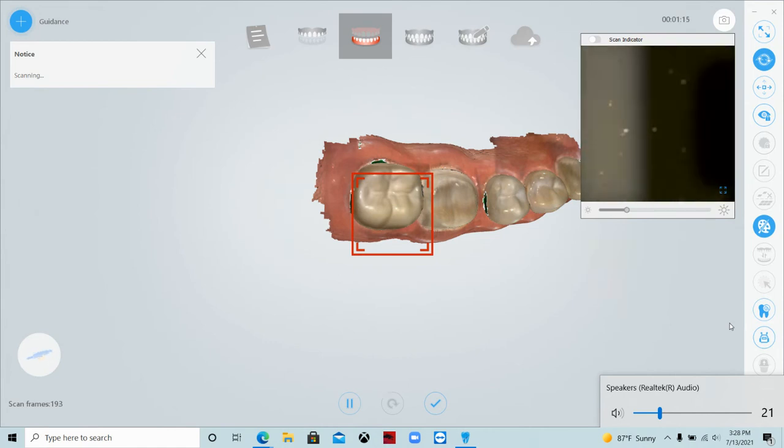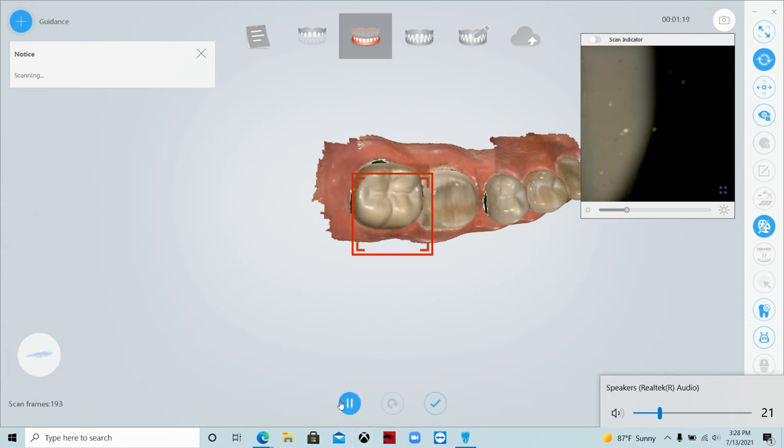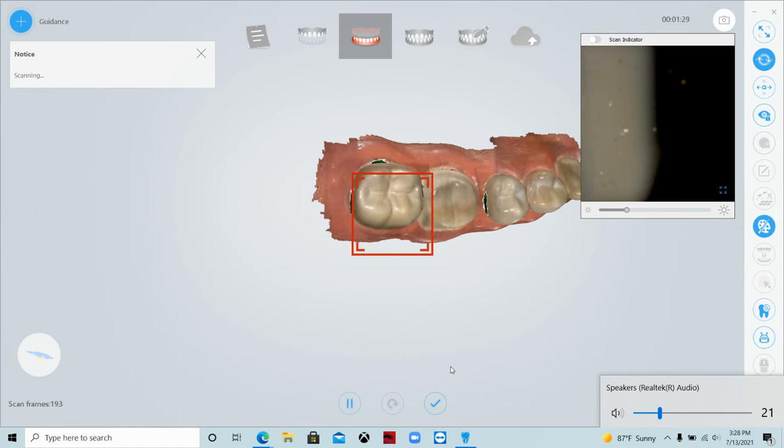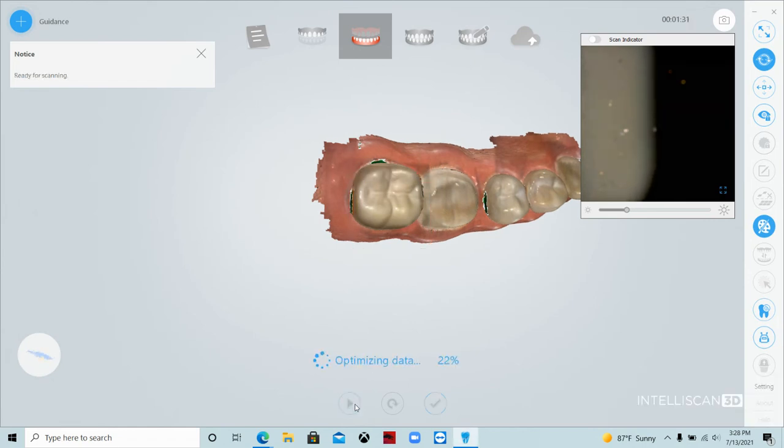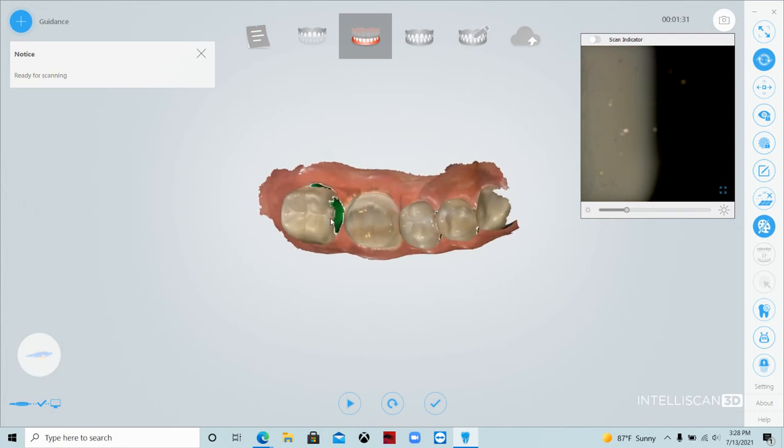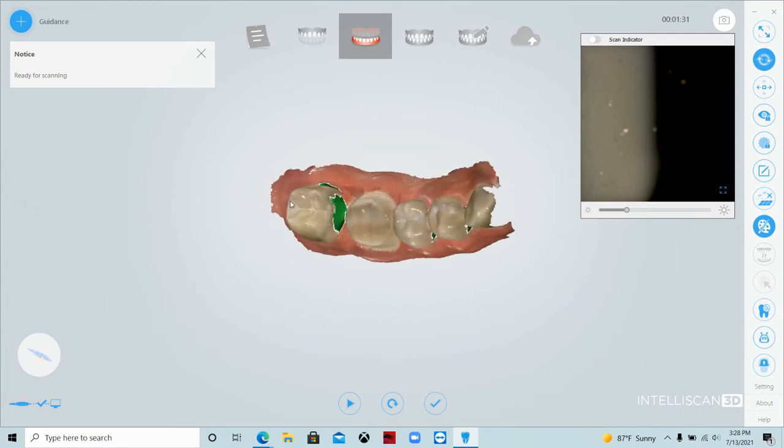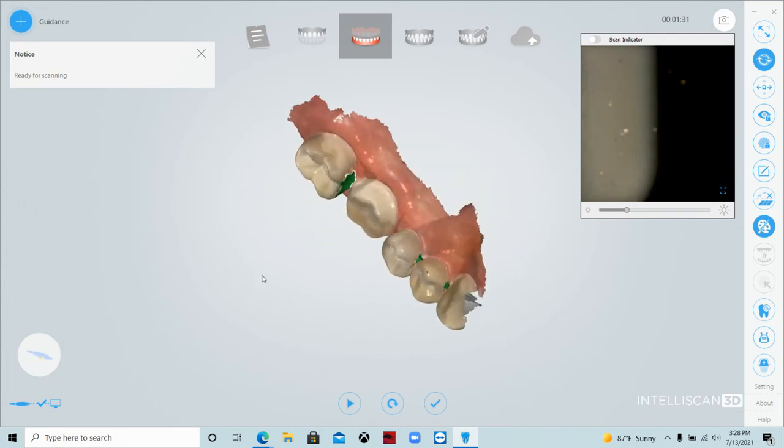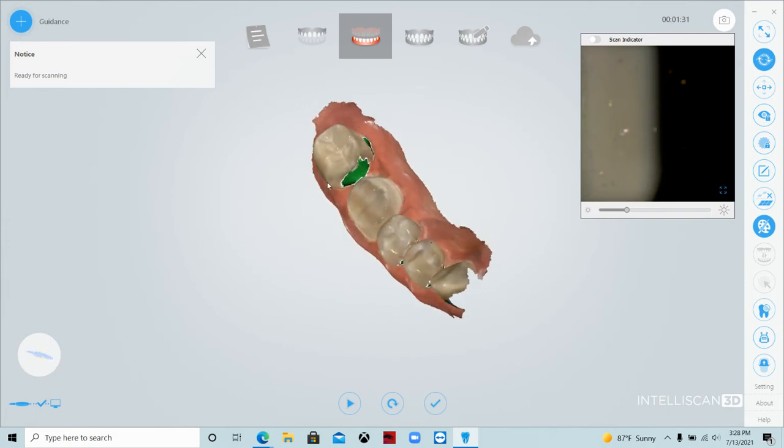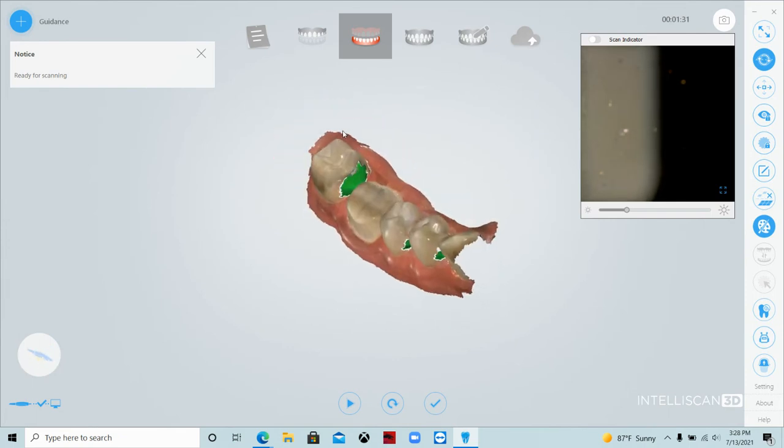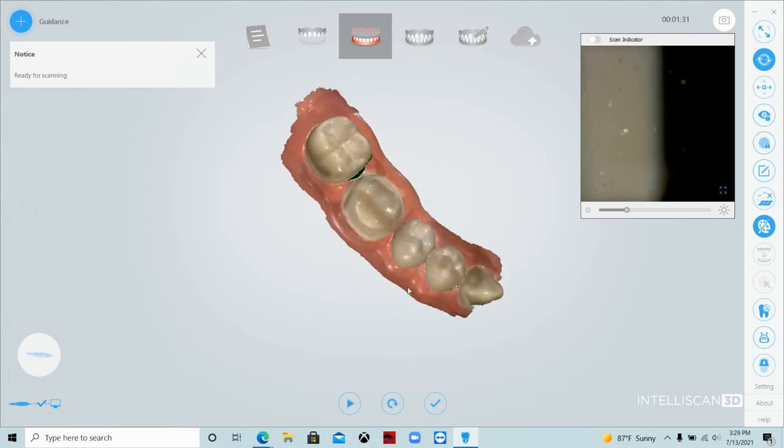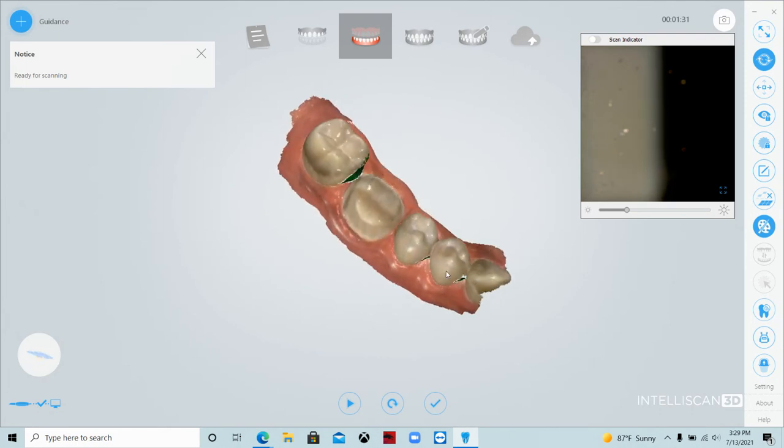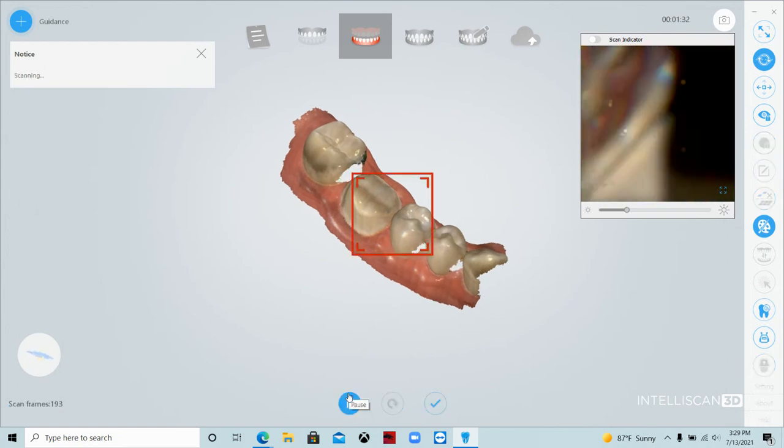I pulled the wand out of the mouth and I have two options below. I can either stop the scan, which is this icon here, or I can save the scan. Only save the scan when you know that it's ready. I don't know that it's finished yet. So I'm just going to hit the stop. When I hit the stop, I now can use my left mouse to look at my scan in all different directions. And I can see the bright green shows me where I didn't scan. If this were crown prep, those small holes on the premolars are fine, but the large hole on the contacts is not fine.